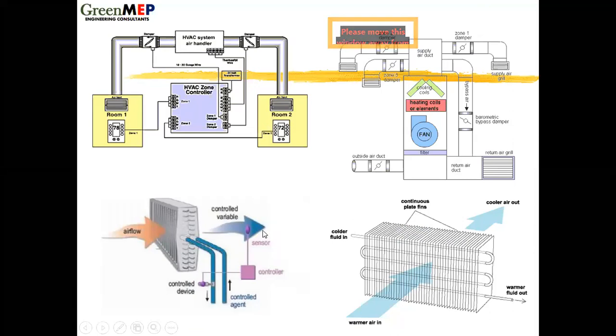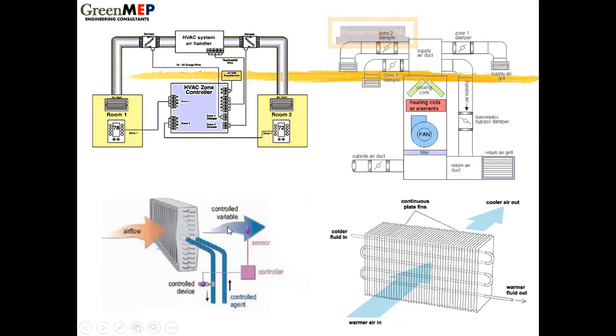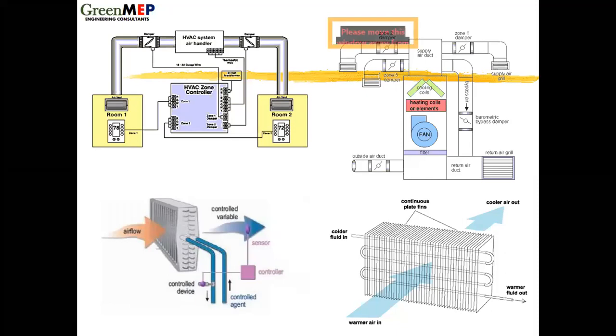You can see air temperature control, temperature control problem 1. And there's a speed control problem, fan speed control, problem 2, adjusting the air flow rate. And then when the valve opens, the chilled water pumps' speed goes up. So there's a pump speed control. Whether it's a fan or a pump or compressor, all these are called turbomachineries, powered by motors. Basically, your computer is communicating with the motor controls. Every motor has a controller.